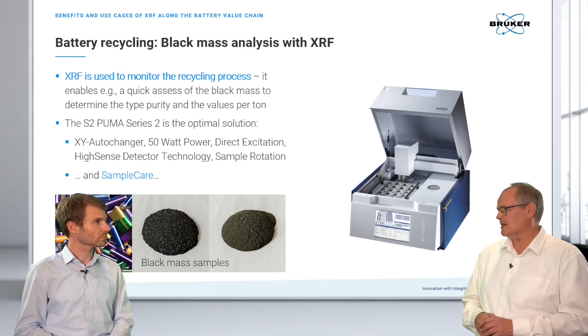When we look inside, we see here the sample. Of course, it's a cup with a thin foil on the bottom. It may happen that the foil breaks and the powder is released. Therefore, on the one hand, we need to avoid contamination of the X-ray tube. This is a pretty expensive component, and therefore the S2 Puma has a filter wheel in front of the X-ray tube, with a filter to protect the X-ray tube head. So at the point of breakage of the foil, the powder will not enter and damage the X-ray tube itself.